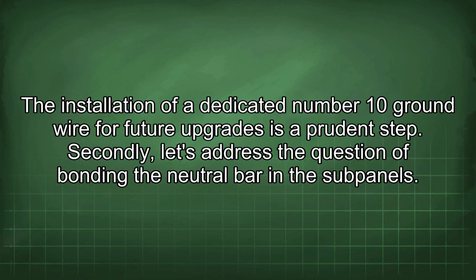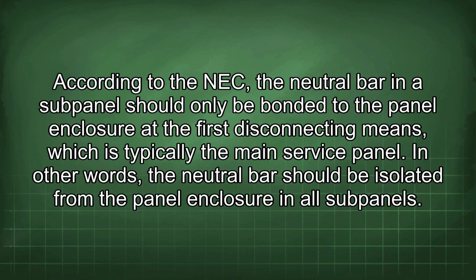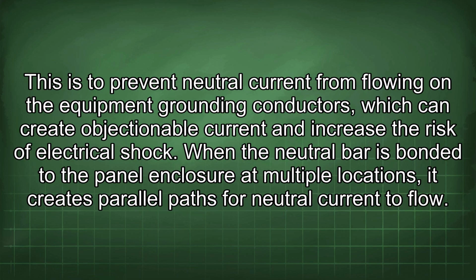Secondly, let's address the question of bonding the neutral bar in the subpanels. According to the NEC, the neutral bar in a subpanel should only be bonded to the panel enclosure at the first disconnecting means, which is typically the main service panel. In other words, the neutral bar should be isolated from the panel enclosure in all subpanels. This is to prevent neutral current from flowing on the equipment grounding conductors, which can create objectionable current and increase the risk of electrical shock.